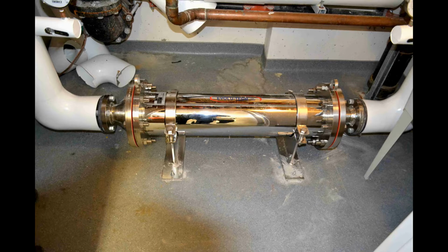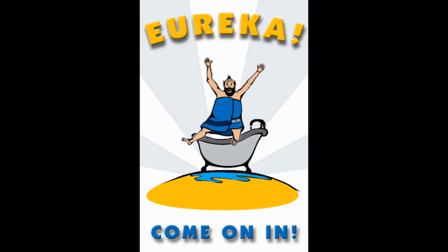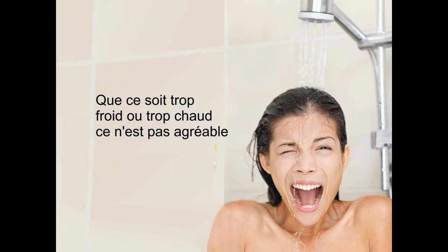At the time, we were getting about 100 complaints out of the 149 apartments, especially from our 3.5 and 4.5 units. A few weeks after installation of the catalytic system back in June 2015, the number of complaints dropped by 98%. The few remaining complaints took root in the poor leak-proofing capacity of certain valves that had been acid cleaned and were worn out by the repeated acid cleanings.